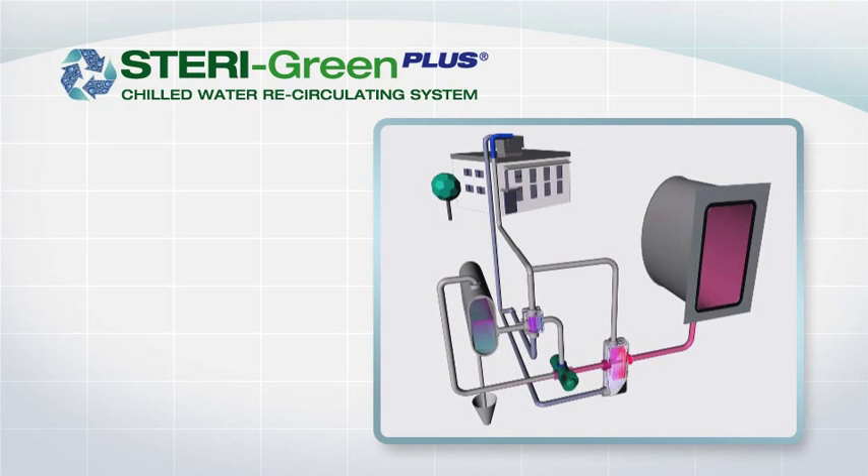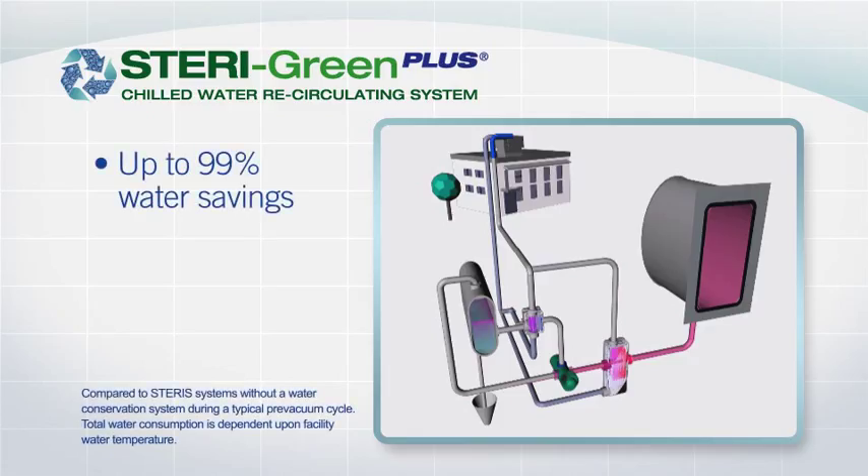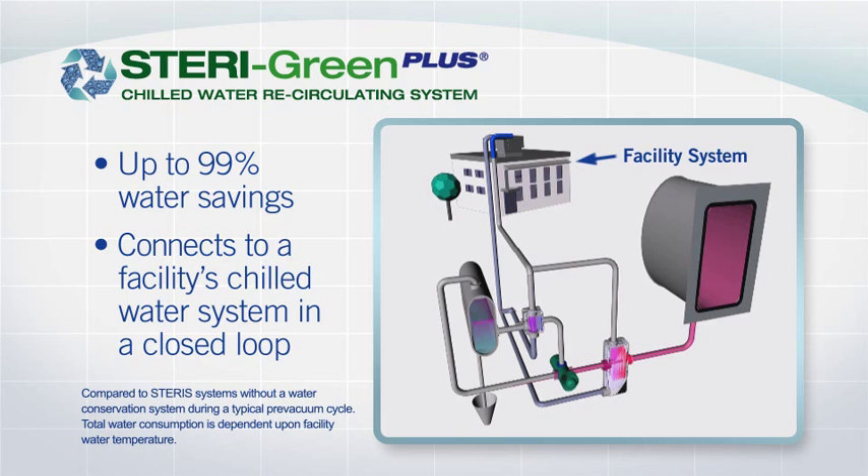Now let's look at the Steri-Green Plus system. This unit truly maximizes water savings up to 99% by connecting to a facility's chilled water system in a closed loop. The chilled water runs through the sterilizer's heat exchangers to provide maximum efficiency in cooling chamber exhaust and vacuum pump water. The chilled water is then returned to the facility's main cooling system.